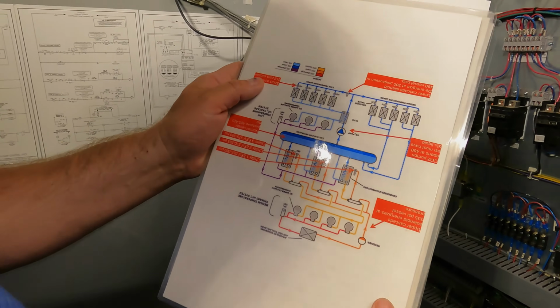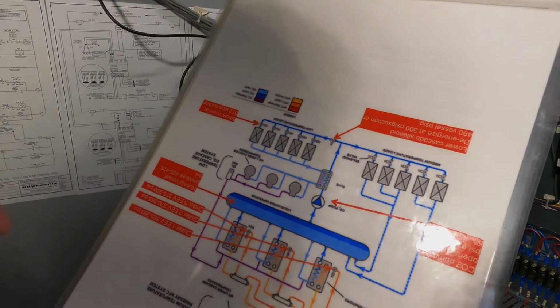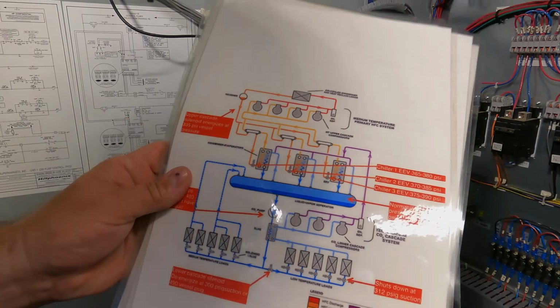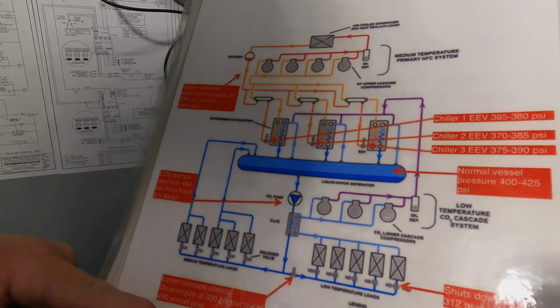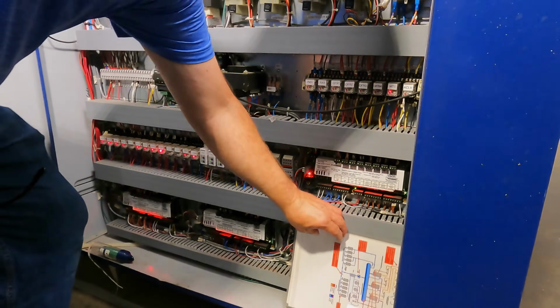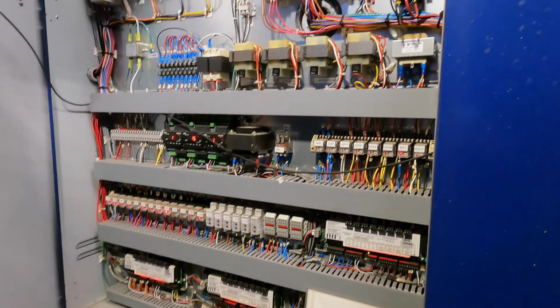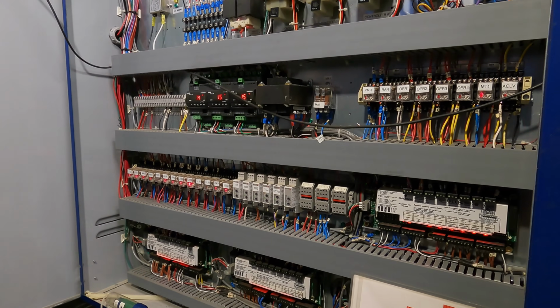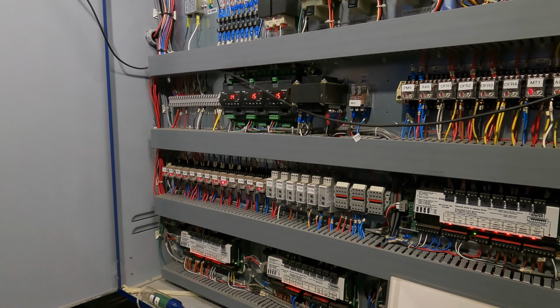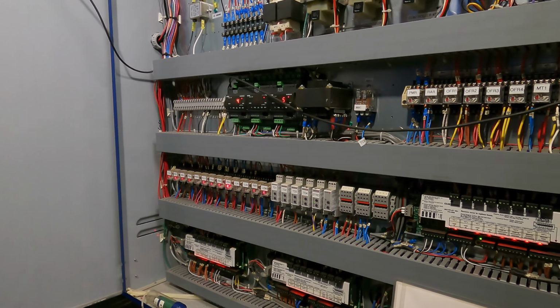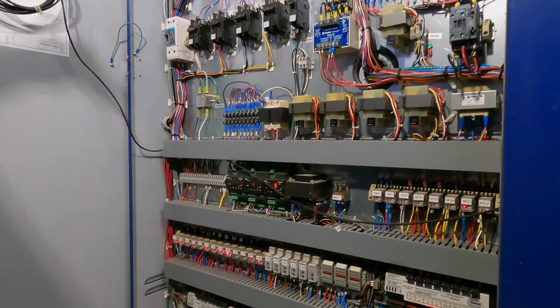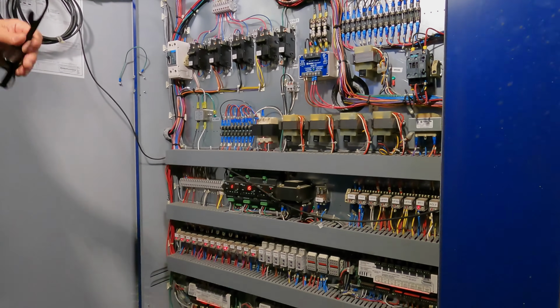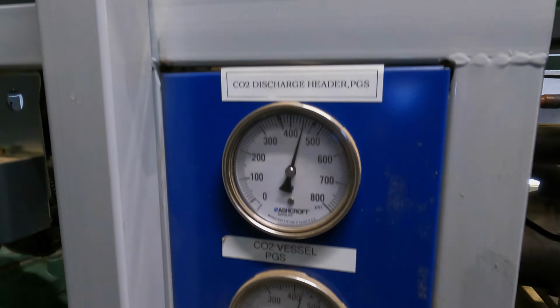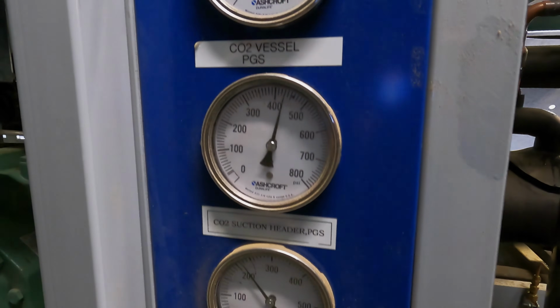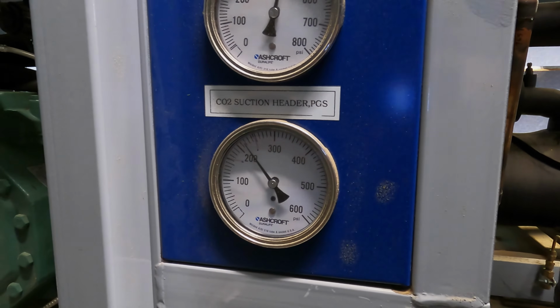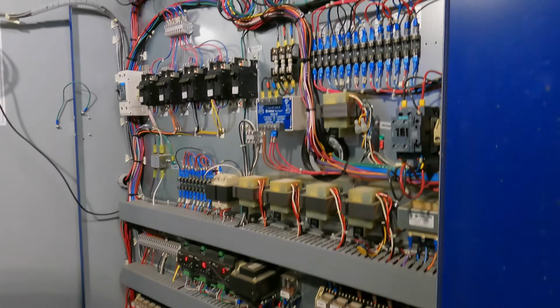And that's a basic diagram of how everything works. Oops, let me turn it the right side up for you. This is the upper cascade, this is the lower cascade. Now, with that said, with the safeties that I was talking about, if we ever have a power failure here and it's off for a long time, when the power comes back on or something fails, we have systems that try to prevent us popping off relief valves on our CO2. CO2 wants to be at a high pressure. It loves being at high pressure. So we want to do everything we can to keep it from doing that.